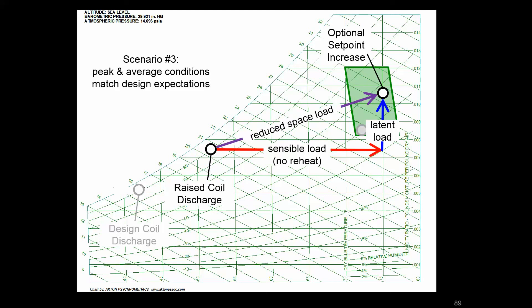It's important to think about the effects from a psychrometric standpoint of when we change set points and what that impact is going to be. In this case, you might argue that it's a low operational impact, but we're able to get rid of that simultaneous heating and cooling that may have been there by design. But with these types of augmented operations, we might be able to really improve the energy usage.